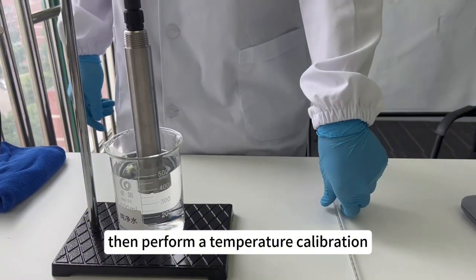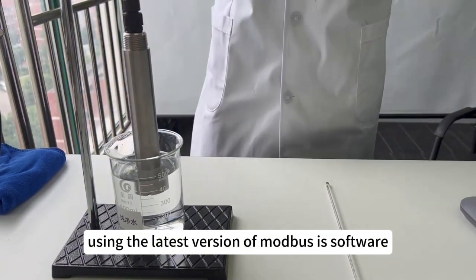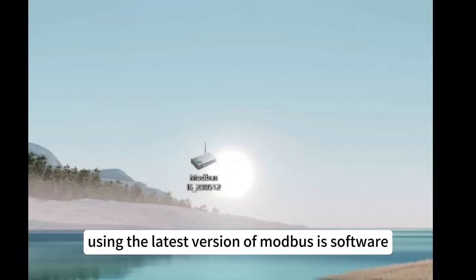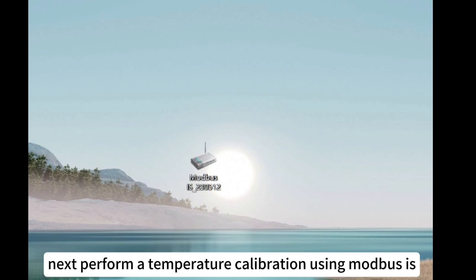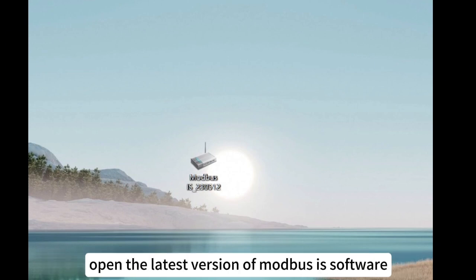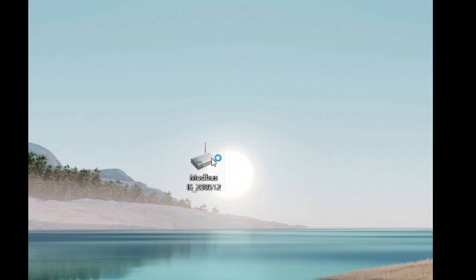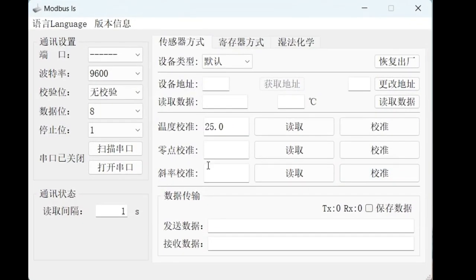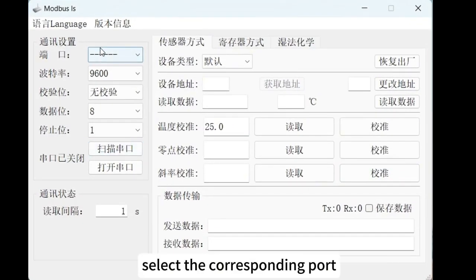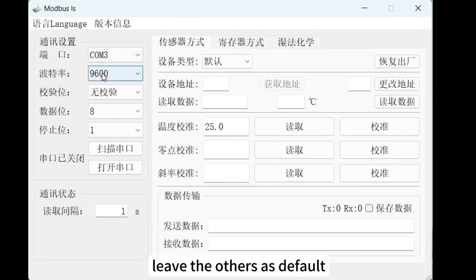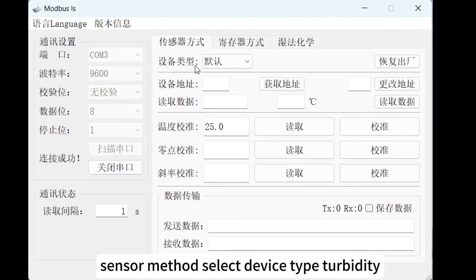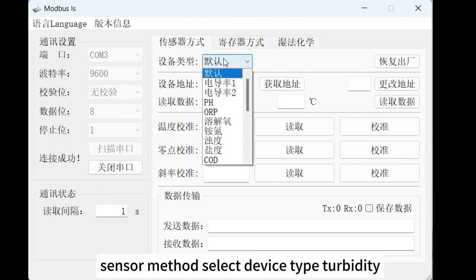Then perform a temperature calibration using the latest version of Modbus IS software. Open the latest version of Modbus IS software. Scan for serial ports. Select the corresponding port. Leave the others as default. Open the serial port. Sensor method, select device type turbidity.